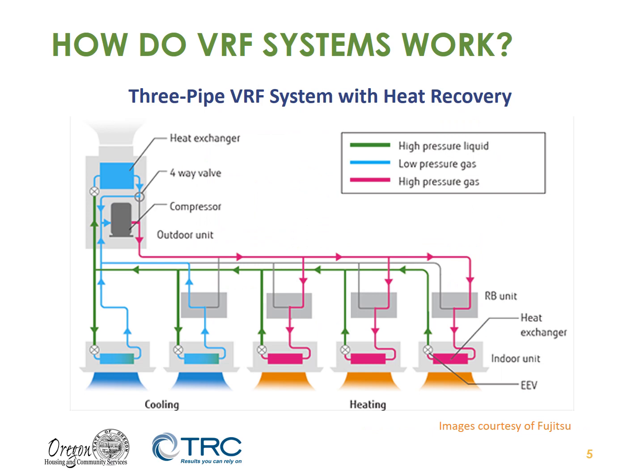In the scenario we have on the screen now, we're looking at the three-pipe VRF system, also referred to as a heat recovery system. In this scenario, we have two gas lines and a liquid line, hence the three-line system. Remember, all heat pumps work by moving heat from one area to another through the processes of compression, expansion, and heat exchange. In a traditional system, when heat is released in a building, there must be some waste cool released from the outdoor unit to the outside.